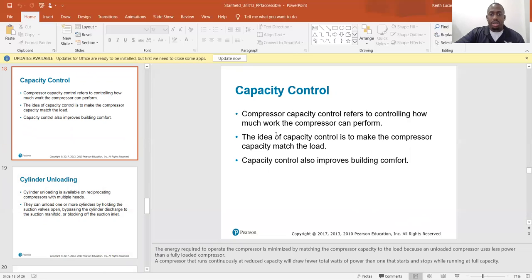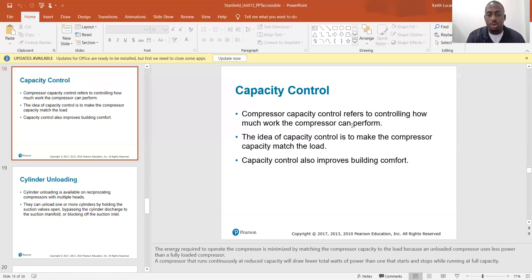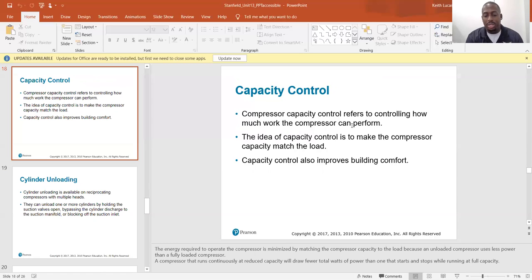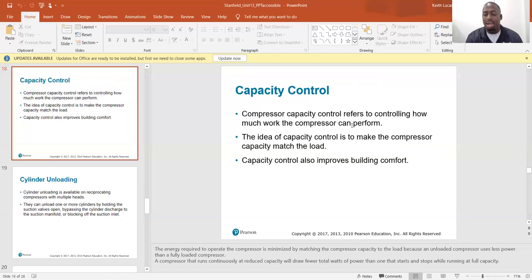Capacity control refers to controlling how much work the compressor performs — the goal is to match the compressor capacity to the load. Capacity control also improves building comfort. The energy required is minimized by matching compressor capacity to the load because an unloaded compressor uses less power than a fully loaded one. A compressor running continuously at reduced capacity will draw fewer total watts than one that starts and stops at full capacity.